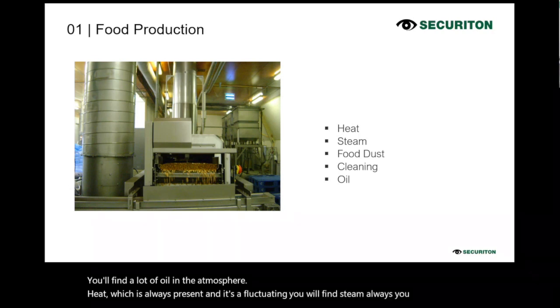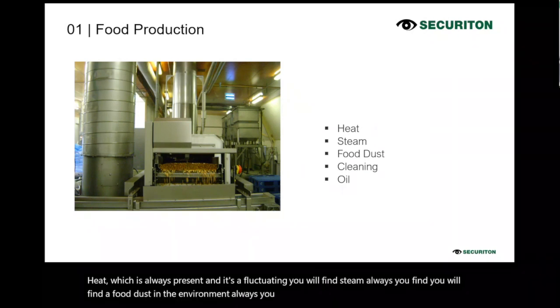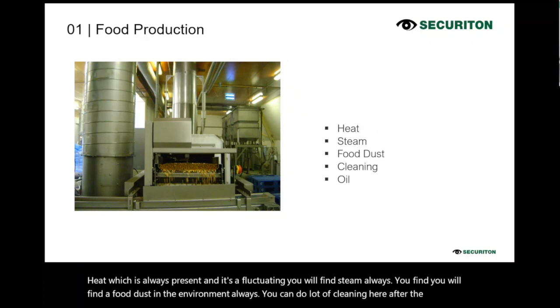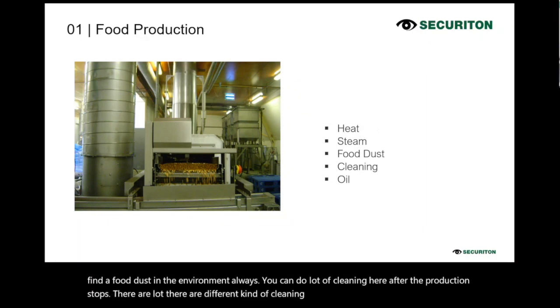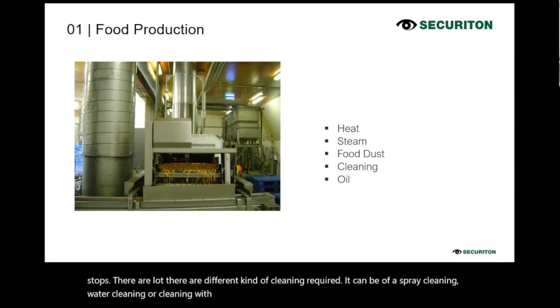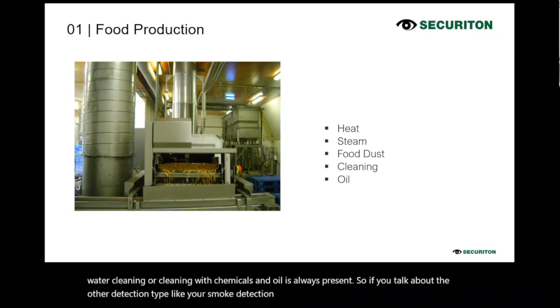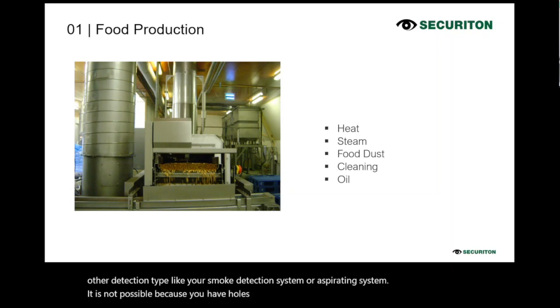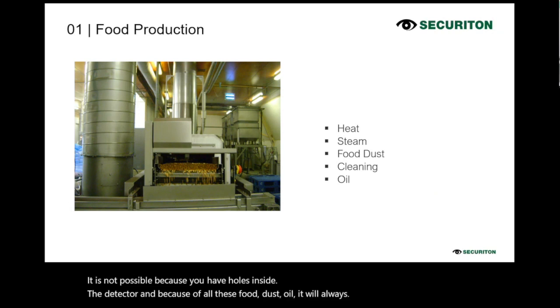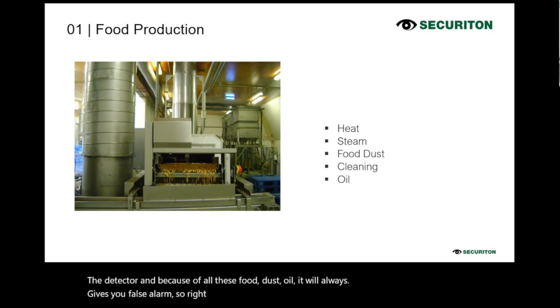You will always find food dust in the environment. A lot of cleaning is done here after the production stops. Different kinds of cleaning are required. It can be spray cleaning, water cleaning, or cleaning with chemicals, and oil is always present. So other detection types, like smoke detection systems or aspirating systems, are not possible because you have holes inside the detector, and because of all this food dust and oil, it will always give you a false alarm. So right now, the best solution available is the linear heat system, and if it gives you an address, then it is an added advantage.